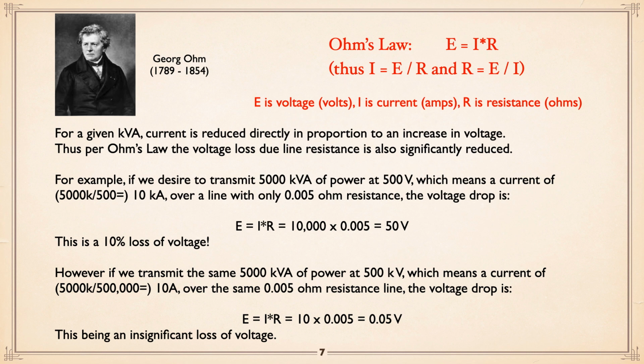Okay? Let's say we want to transmit 5,000 kVA of power at 500 volt. This means a current of 10 kiloamps over a line, which let's say has 0.005 ohm resistance. The voltage drop will be, working through that equation, 50 volt. We started at 500 transmitting over those lines. We've dropped it down by 10%.